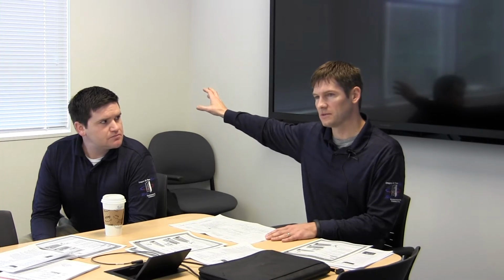So the last time I looked at the fan coil units, the little section where the controls usually is just a flat plate. I don't know, is there a remote control for that or something? These are the fan start-stop, and how much hot water you get is controlled by the control system. There should be an automated logic wall sensor that senses the temperature of that room, has a set point associated with it, and it will turn on and off the fan based on a schedule, and it'll open and close the valve based on room temperature. So it won't have any onboard controls.